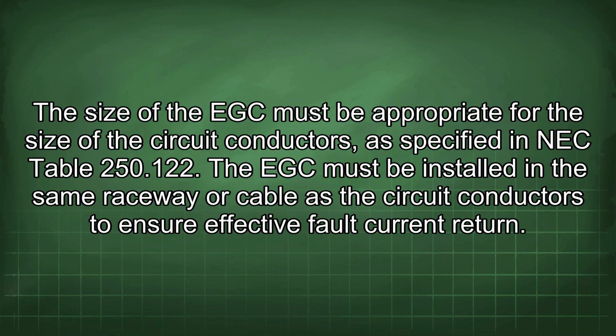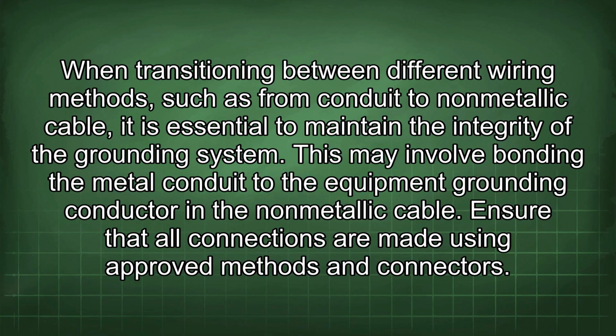When transitioning between different wiring methods, such as from conduit to non-metallic cable, it is essential to maintain the integrity of the grounding system. This may involve bonding the metal conduit to the equipment grounding conductor in the non-metallic cable. Ensure that all connections are made using approved methods and connectors.